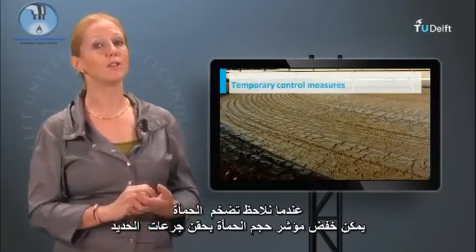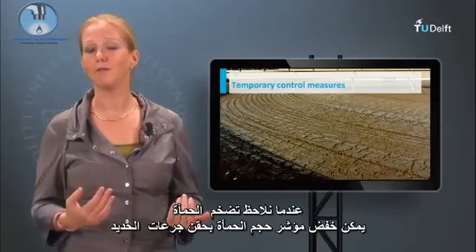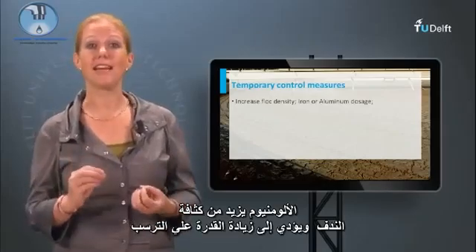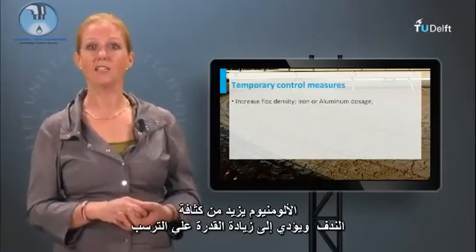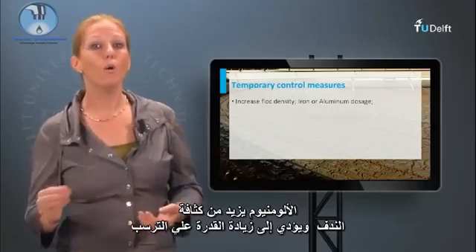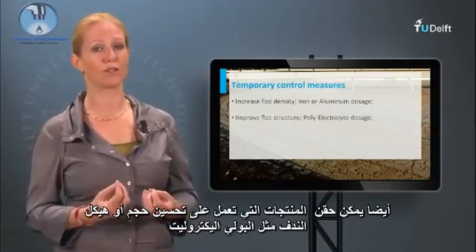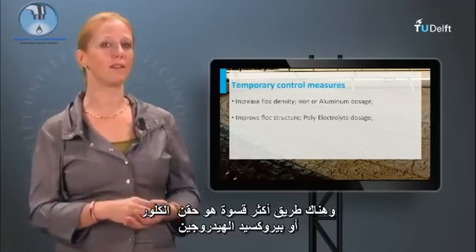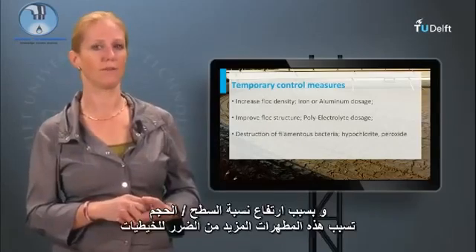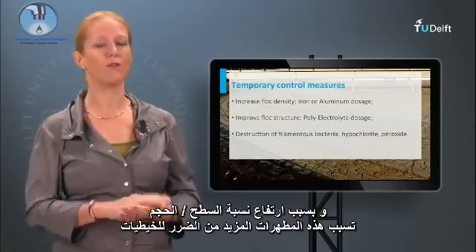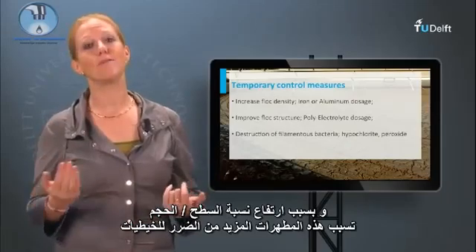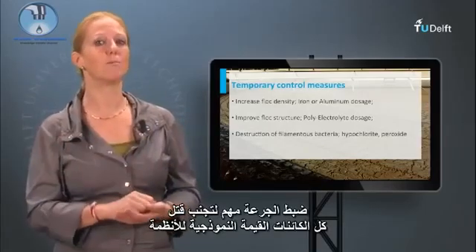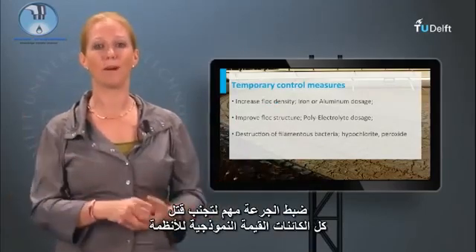When sludge bulking is observed, the sludge volume index can be decreased by dosing iron or aluminium. The aluminium increases the density of the flocks and leads to increased settleability. Also products that improve size or structure of the flocks can be dosed, like poly-electrolytes. A more harsh method is chlorine or hydrogen peroxide dosing. Due to the high surface-to-volume ratio of filaments, these disinfectants will bring more harm to the filaments than to the flock formers. The dosage is important to avoid killing the entire population.